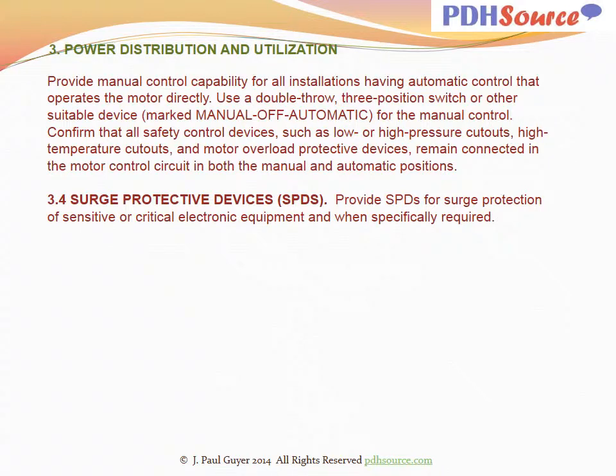Provide manual control capability for all installations having automatic control that operates the motor directly. Use a double throw, three position switch, or other suitable device marked manual, off, automatic for the manual control. Confirm that all safety control devices, such as low or high pressure cutouts, high temperature cutouts, and motor overload protective devices, remain connected in the motor control circuit in both the manual and automatic positions.